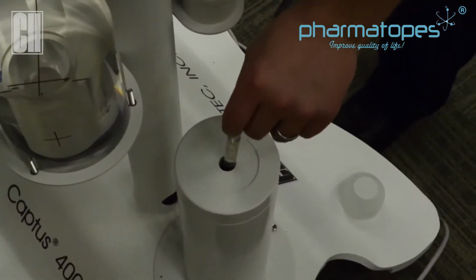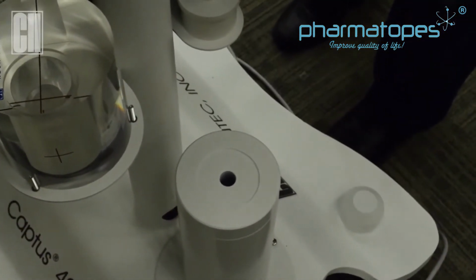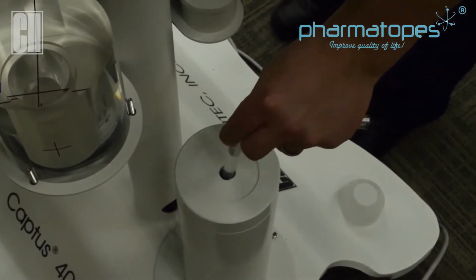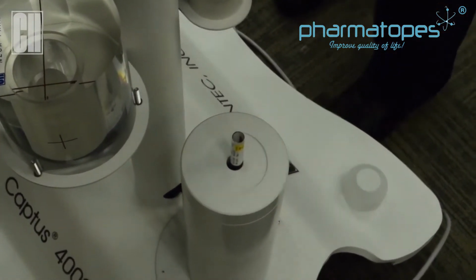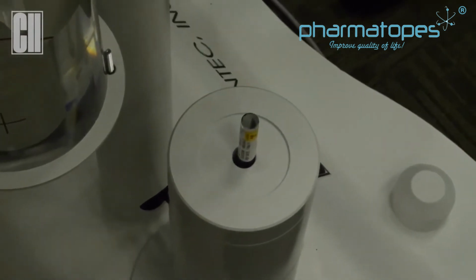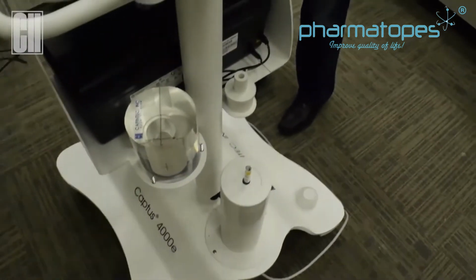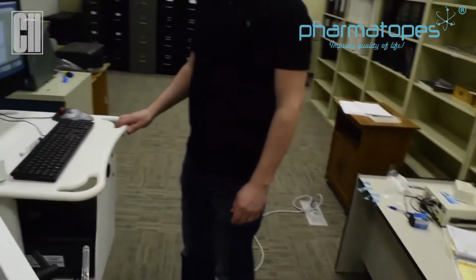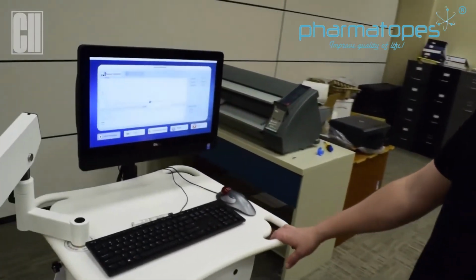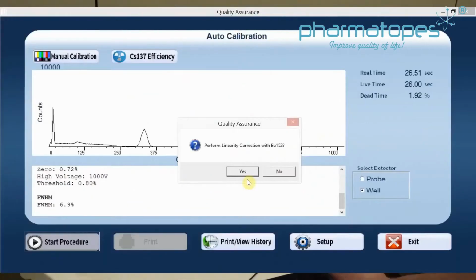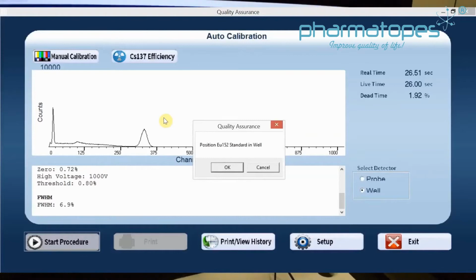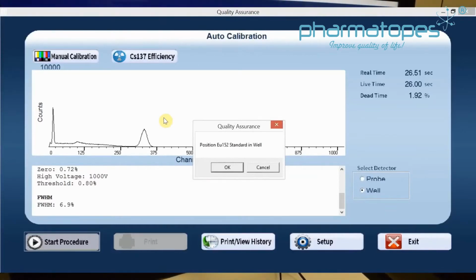So remove the cesium source and position your europium source into the well. Again, black tip down. Once in position, we can click yes to linearity and then OK to start the calibration.